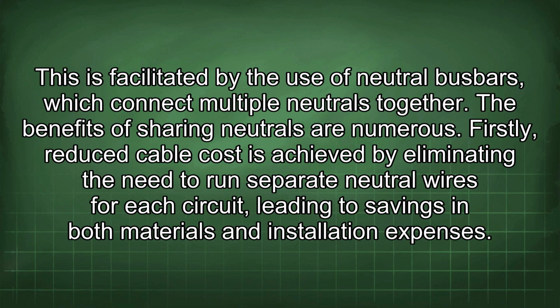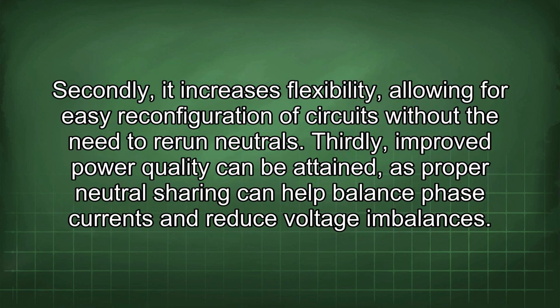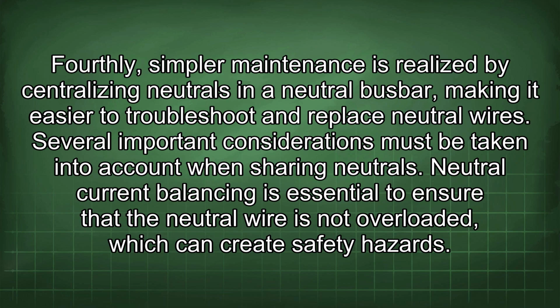The benefits of sharing neutrals are numerous. Firstly, reduced cable cost is achieved by eliminating the need to run separate neutral wires for each circuit, leading to savings in both materials and installation expenses. Secondly, it increases flexibility, allowing for easy reconfiguration of circuits without the need to rerun neutrals. Thirdly, improved power quality can be attained, as proper neutral sharing can help balance phase currents and reduce voltage imbalances. Fourthly, simpler maintenance is realized by centralizing neutrals in a neutral busbar, making it easier to troubleshoot and replace neutral wires.